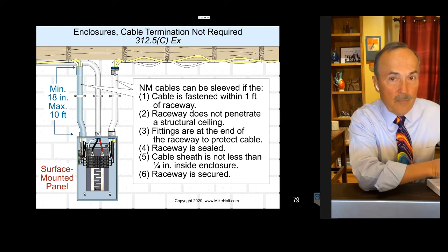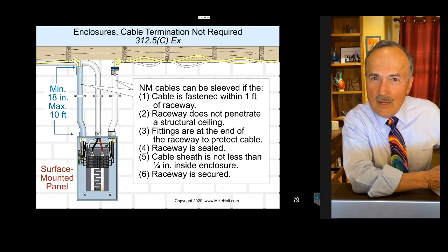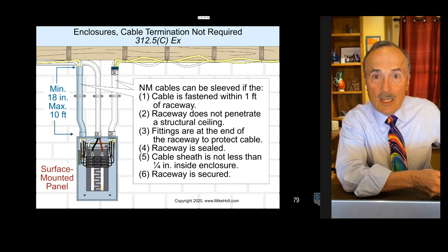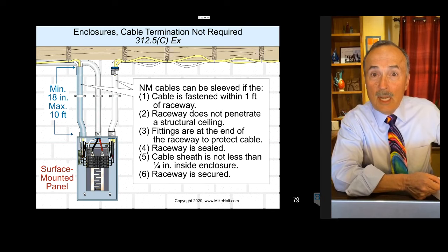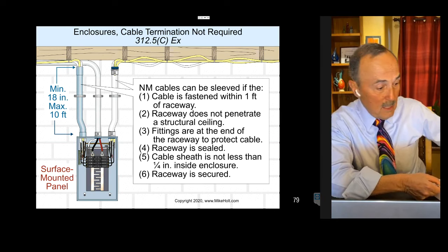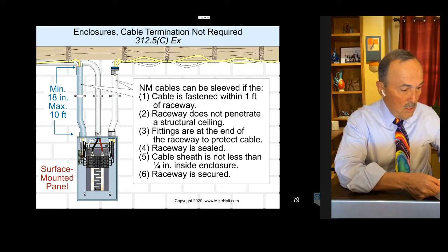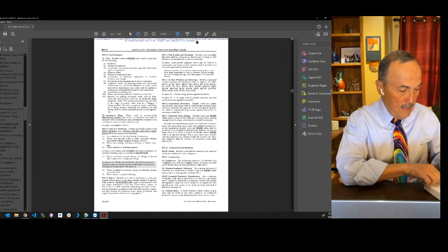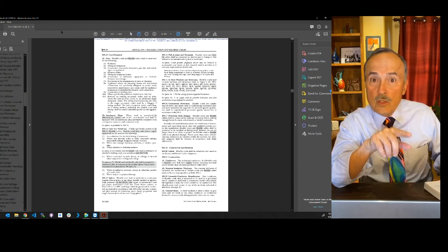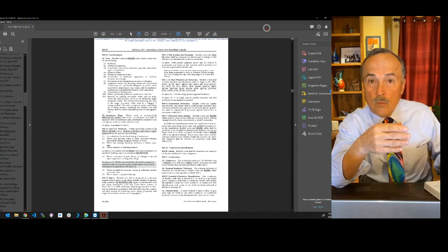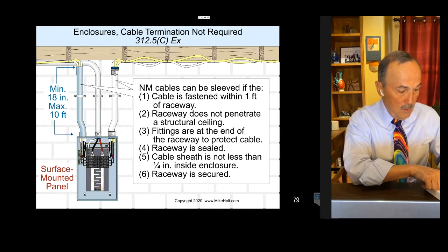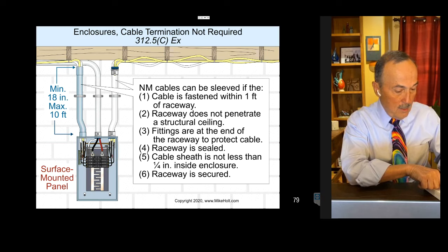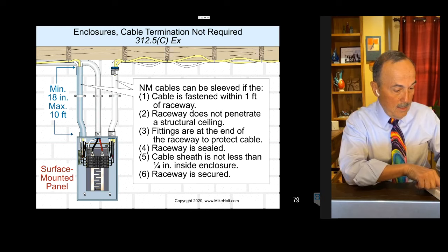I think, guys, go to 312.5C. I think that graphic is missing in there. You know what? I really don't like me not using a code book. It was really bothering me yesterday. They say, I think it's this rule, I think it's that rule, because between the 2020 code and the 2017 code, there's been a lot of changes in Article 310, which is where I spent a lot of time. 312.5C exception. I thought this exception used to say that it was only permitted on surface mounted wire methods.